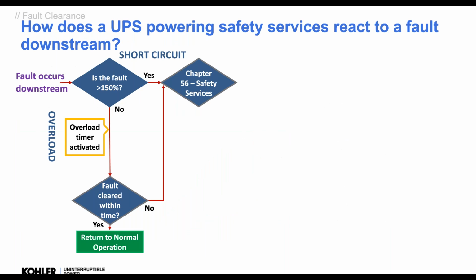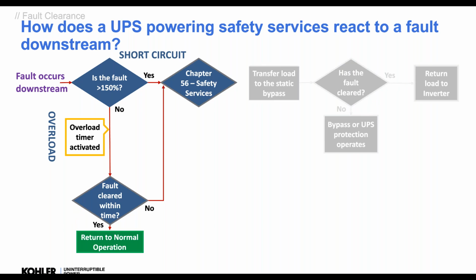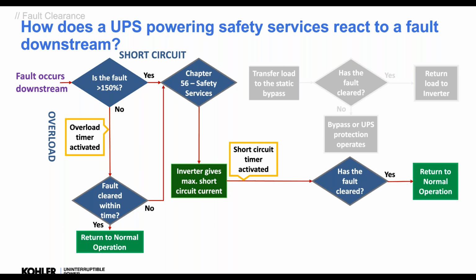So for safety services with a UPS, where we said is the bypass available, we cannot rely on that bypass being available, because it might be an emergency situation where we have to clear the protective device on inverter, on battery, because there is no mains. So that means the inverter short circuit capability has to be used to clear the downstream device, and do it. If it doesn't, it doesn't comply. It's as simple as that. Just because it turns off isn't a reason to say it's safe. We have to clear the fault because we want to keep everything else running.